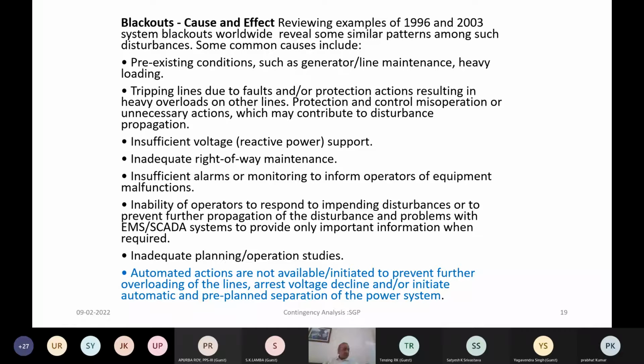Earlier, when such a phenomenon used to happen, in distance relays the line used to trip on a three-phase fault. Actually, the reduced voltage and increased load used to result in activation of zone 3, and a three-phase fault in zone 3 used to be a reason for tripping. So usually engineers used to report that this tripping is on account of power swing. But of course, with the new numerical relays, understanding has improved, and there are features to tackle this, which we'll discuss in the afternoon.